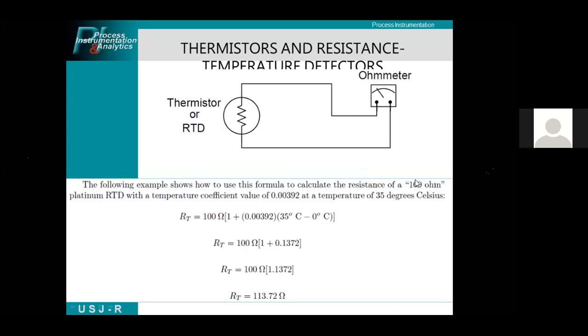So what does it mean? If you have a 100 ohm platinum RTD, it can reach up to 113.72 ohms at 35 degrees Celsius. The higher the temperature, the higher the resistance also for this RTD. So it increases as the temperature increases. You can compute also, let's say, if the temperature is at 50 degrees. You can say that the resistance of this RTD at 50 degrees also increases from 113 to something.